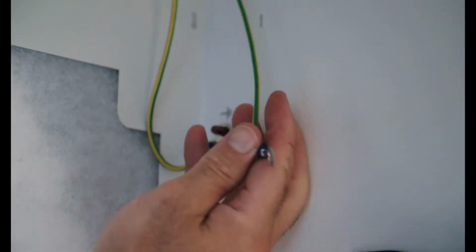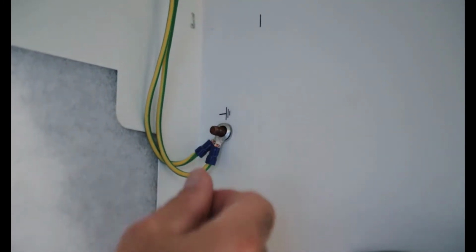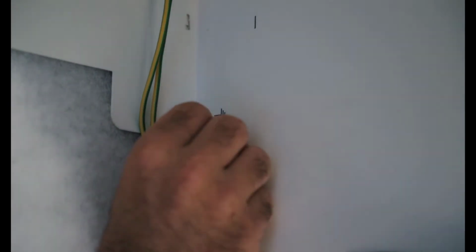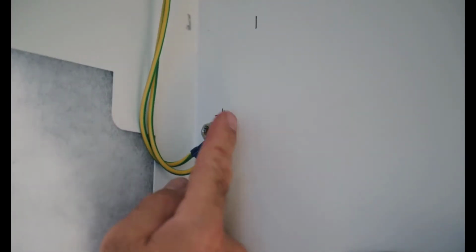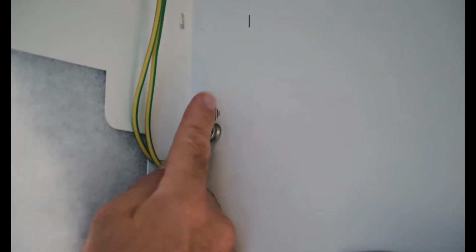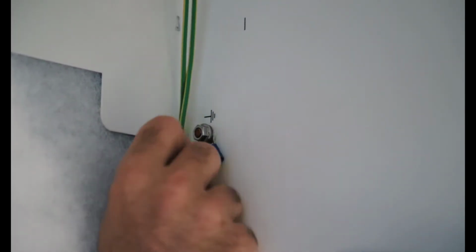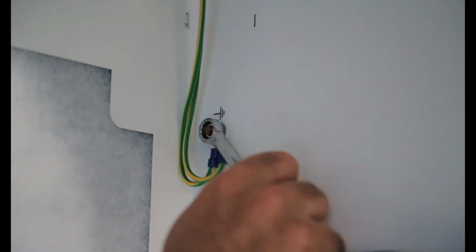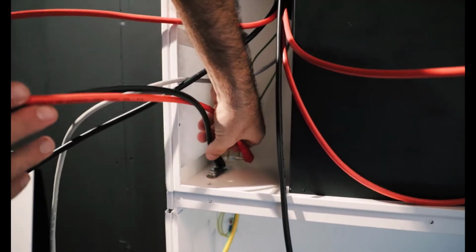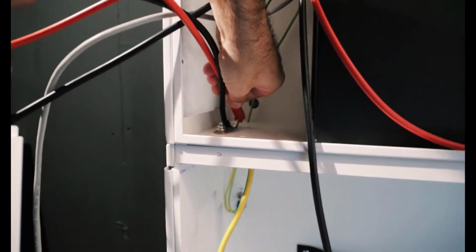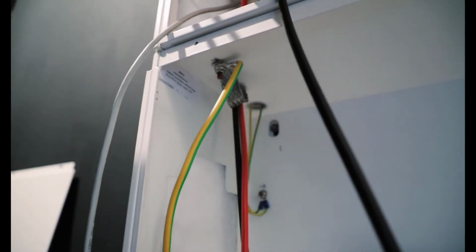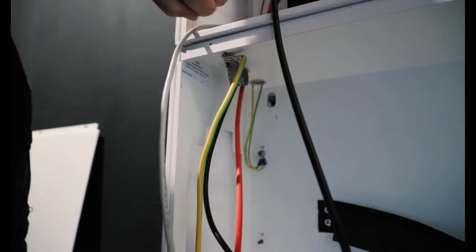So for the sake of simplicity, what we do is pass down those 2 earth cables from batteries 1 and 2, which we already fitted, and terminate them on one of the earthing pins in the extension housing. You'll find that there's earthing pins all the way down through the extension housing as well as in the main unit. For, again, sake of simplicity and ease of installation, what I recommend is making sure that you terminate those in locations that are easily accessible. They don't necessarily need to be terminated adjacent to the batteries themselves.